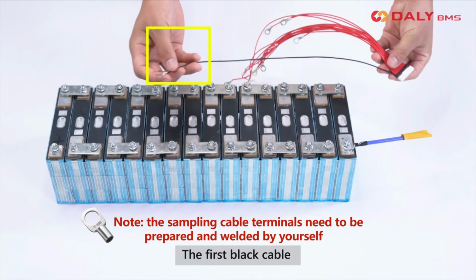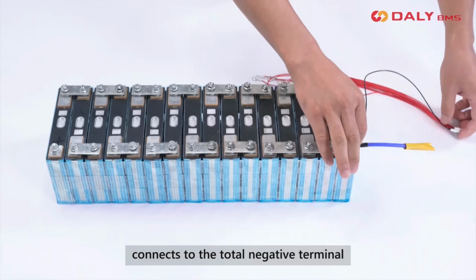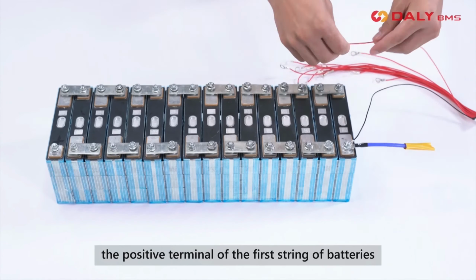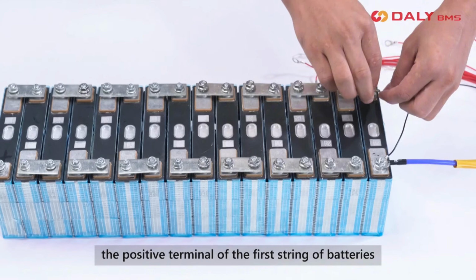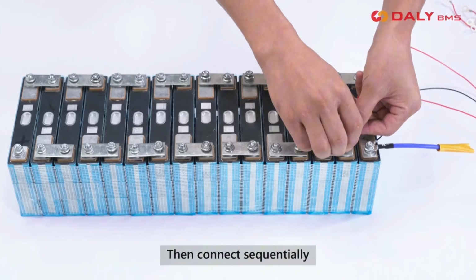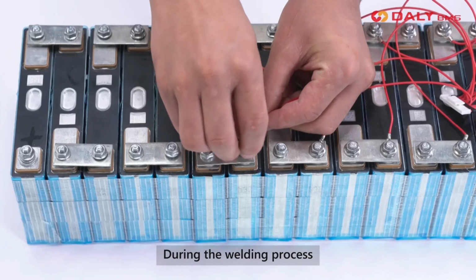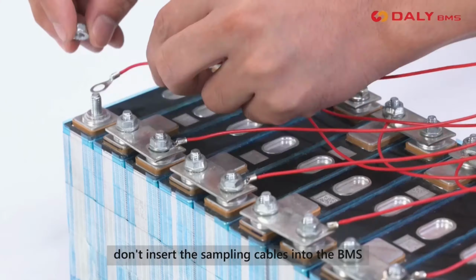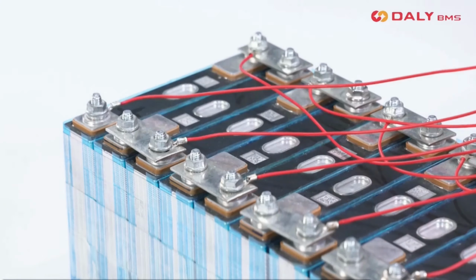The first black cable connects to the total negative terminal. The second cable connects to the positive terminal of the first string of batteries. Then connect sequentially. During the welding process, don't insert the sampling cables into the BMS. Secure again.